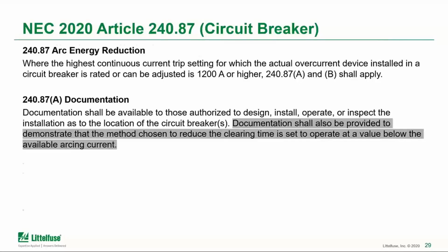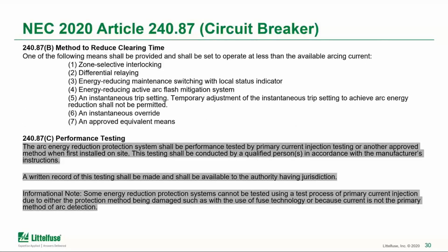the energy reduction. So the specific items mentioned here: zone selective interlocking, differential relaying, energy reduced maintenance switching, active arc flash mitigation relays, or an instantaneous trip setting, or an instantaneous override. So those are specific items that are mentioned.